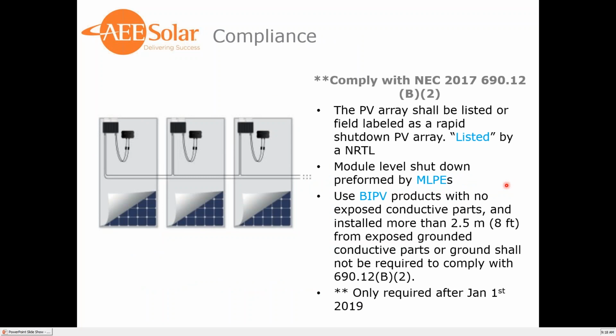Compliance. So they give three different ways to comply with rapid shutdown. The first is to have the entire array field labeled as a rapid shutdown PV array by an NRTL, or module level shutdown performed by MLPEs, or if the system is installed with no conductive parts, essentially using BIPV, building integrated PV parts with no exposed conductive parts, installed more than 8 feet from exposed grounded conductive parts or ground, it shall not be required to comply with 690.12.